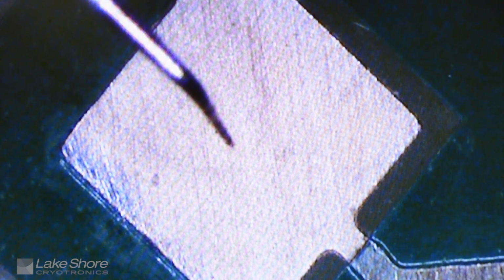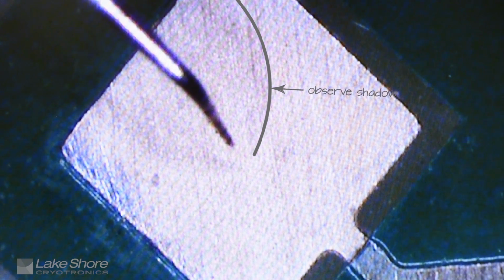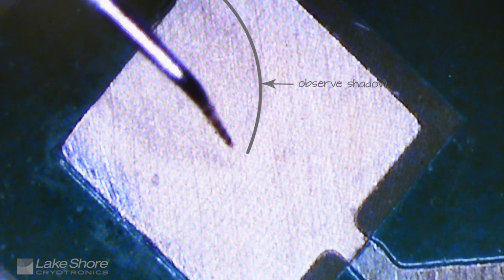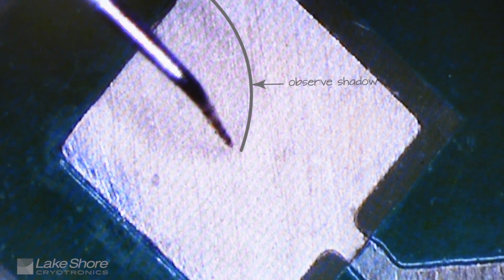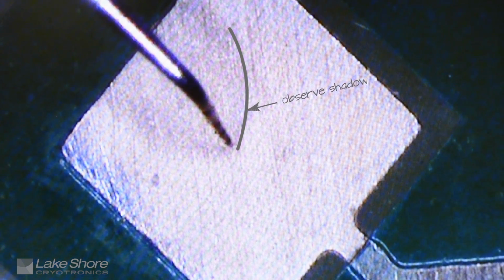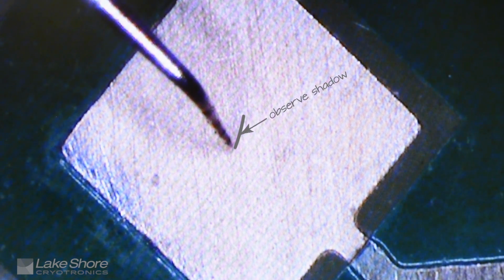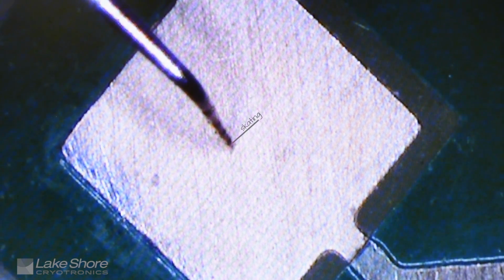Continue lowering the probe slowly. Visually observe the shadow of the probe tip on the sample. Probe tip contact with the sample can be seen by observing when the shadow of the probe tip meets the actual probe tip. Once the probe tip is landed, indicated by a slight forward movement known as skating, continue lowering the probe tip for a consistent amount of overtravel.